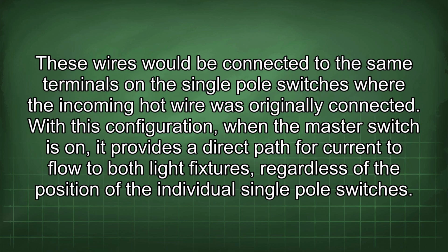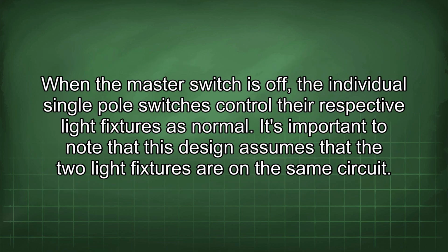These wires would be connected to the same terminals on the single pole switches where the incoming hot wire was originally connected. With this configuration, when the master switch is on, it provides a direct path for current to flow to both light fixtures, regardless of the position of the individual single pole switches. When the master switch is off, the individual single pole switches control their respective light fixtures as normal.